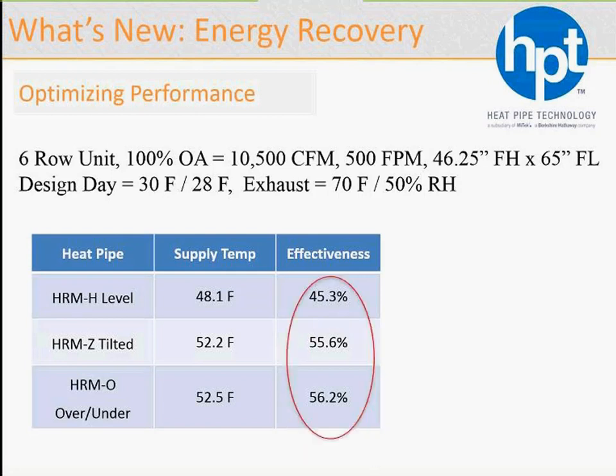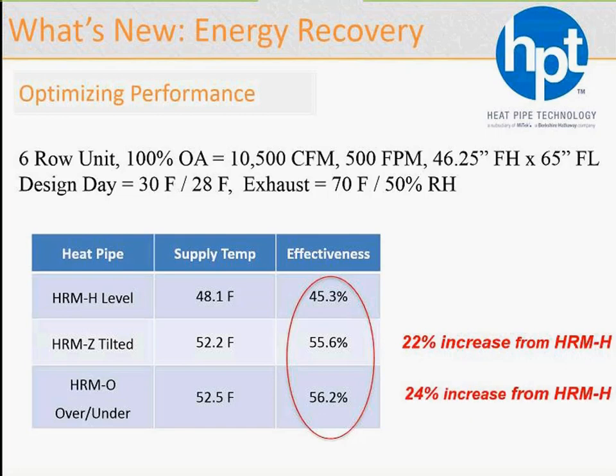What's important here is effectiveness. This is basically translated into the temperatures on the left. The HRM level is 45.3%, certified performance, as we said earlier. The tilted, which is optimized for the season with the most BTUs to recover, jumps to 55.6, and we do even better with the HRM over-under, which is kind of 90 degrees from horizontal. Improvement percentage-wise from HRM level to tilted is 22%, and to the upright increases even better to 24%.